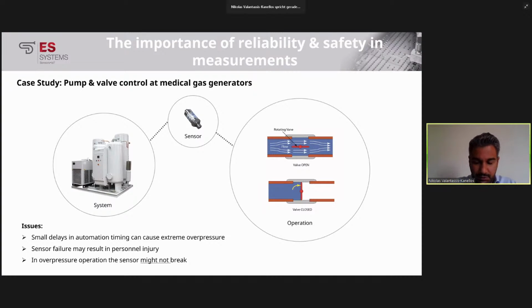And this is a tricky operation because imagine you're a manufacturer in the USA, let's say, and you create medical gas generators and you ship these generators to Europe or to Asia. The equipment is installed at the hospital, and after a couple of months of operation, you get a call from the customer saying that the equipment does not work and is faulty, and he wants his money back and wants to return the equipment.